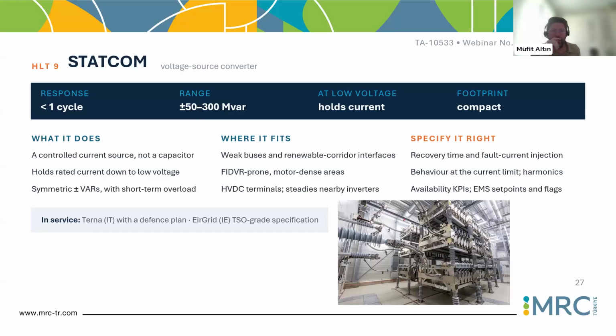before installation, of course. Mainly, the STATCOM is a voltage source with current control. It creates the voltage using the IGBT elements in its system, and when it creates the voltage, the current is controlled in the upper level. One more level up, you can control the Q voltage according to your system. The DC voltage is important; it is automatically controlled on the DC side to create the voltage.